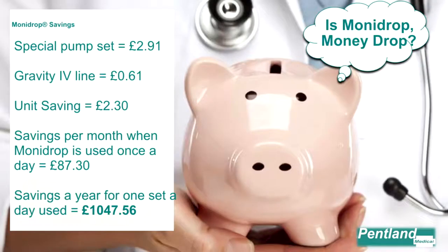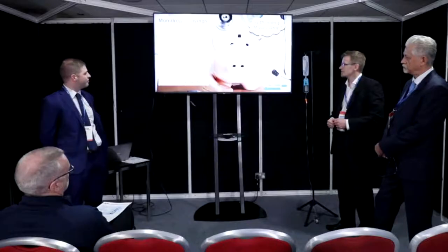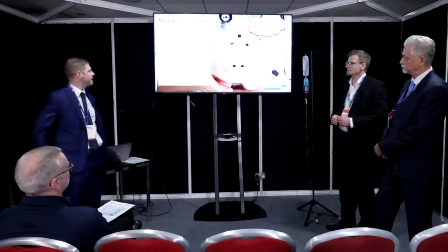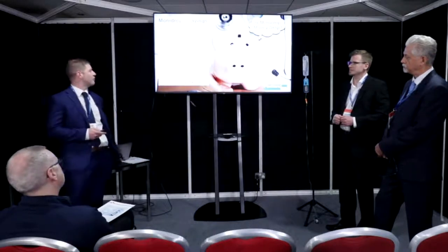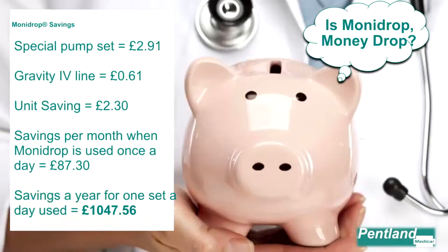On this slide, we highlight the difference between the unit costs of a gravity IV line and a pump giving set. In the bottom part, we highlight the potential monthly and annual savings based on just one gravity set per day in place of an equivalent pump set. So potentially over £1,000 per annum worth of savings based on the use of only one Monidrop. Many more savings could be realised through extensive use of Monidrop throughout the hospital wards.